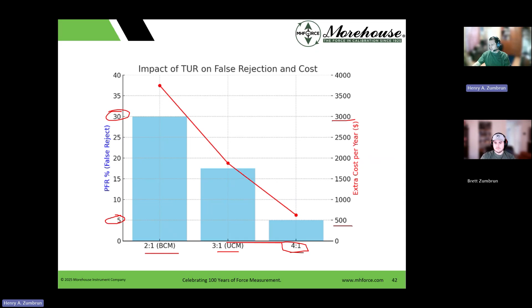If you have three technicians that are all making mechanical measurements, as long as they can align the load cell and wire it up correctly, the automation is going to make the repeatability between those technicians next to nothing. But if it's a manual process where they actually have to hold and control the force with some kind of pressure pump or valve or jack or something else, there's going to be more variation in that process, which is going to kick up the overall measurement uncertainty, and more of this is going to happen.